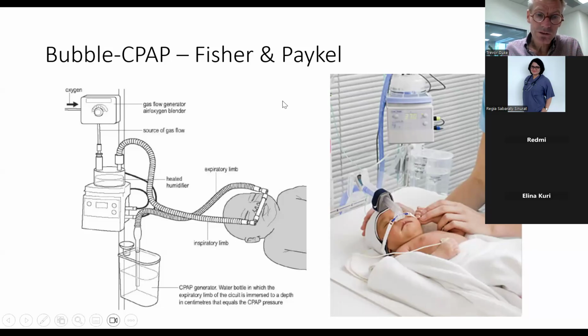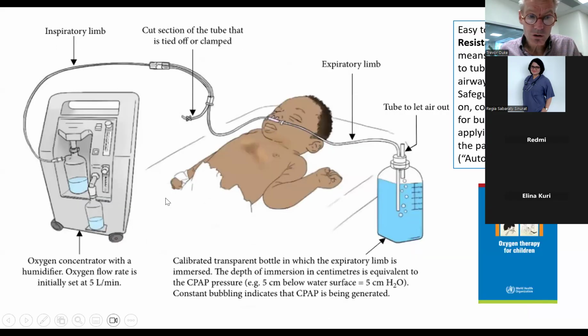It's an elegant machine, but you still need an oxygen source. Whereas with the oxygen concentrators, your oxygen source is the concentrator. Now, this is the first type of bubble CPAP that was used with these concentrators. It just used some oxygen tubing and standard nasal prongs. The benefit of this is they're easy to make and readily available. With nasal prongs, all you do is cut them down so you've got an inspiratory limb and an expiratory limb. I won't go through that too much.